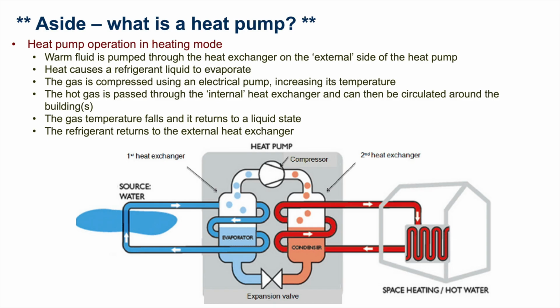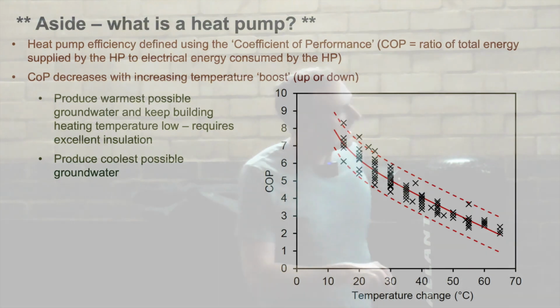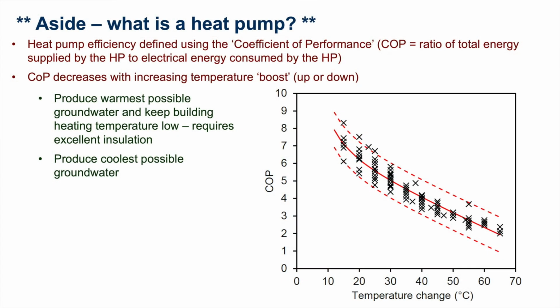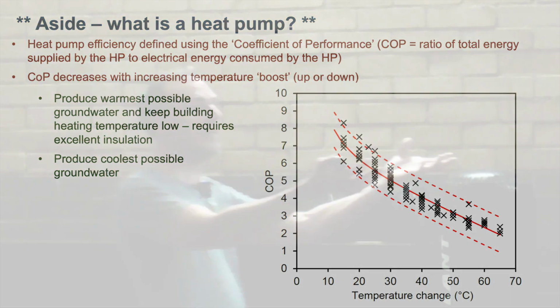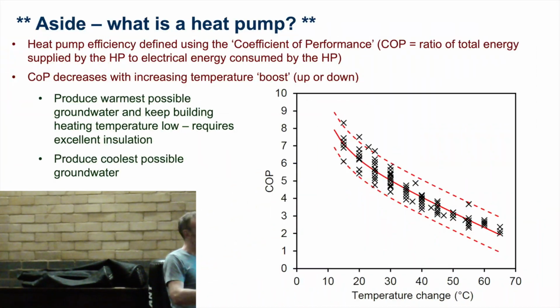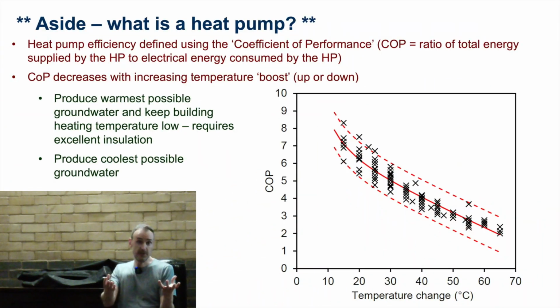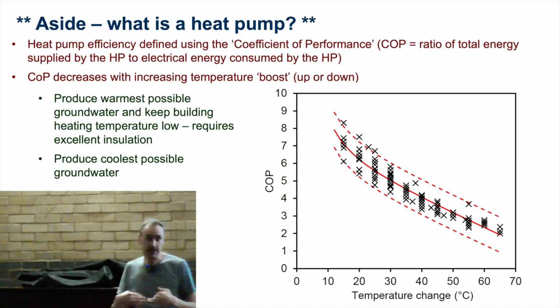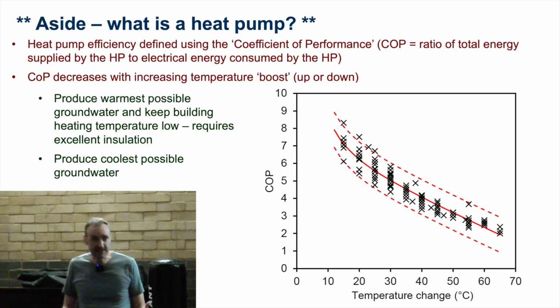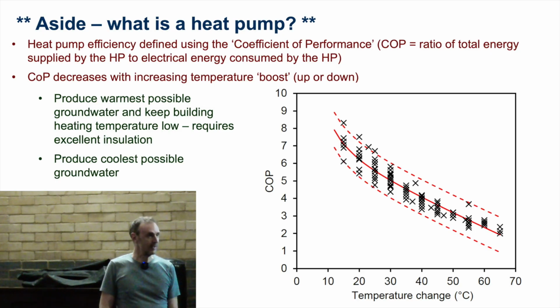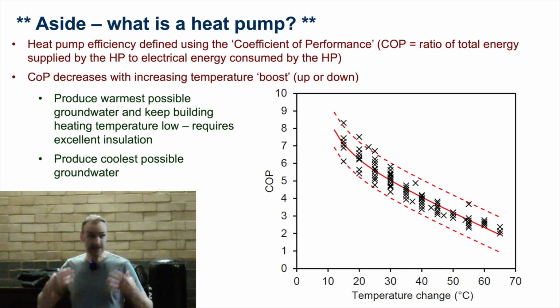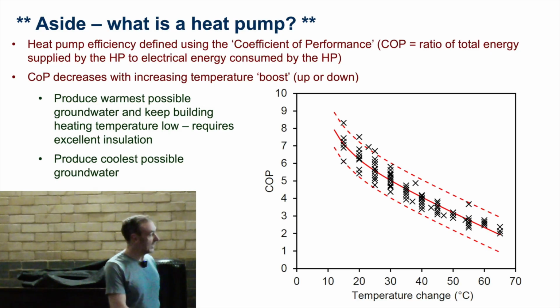With heat pumps, as most people are aware, the less you have to change the temperature, the more efficient the heat pump will be. They're measured by something called the coefficient of performance — the ratio of heating energy out to electrical energy in. A good heat pump puts out 4 units of heating energy for every unit of electrical energy in, which is why it's so much better than a direct electrical heater, like a fan heater, which only gives 1 unit of heat for 1 unit of electricity. A heat pump should be 4 times better than that when working well, even higher if you can keep the temperature boost down.